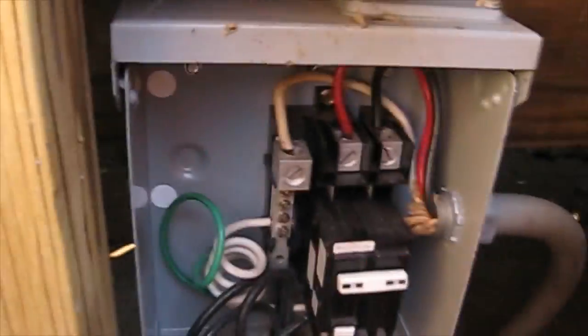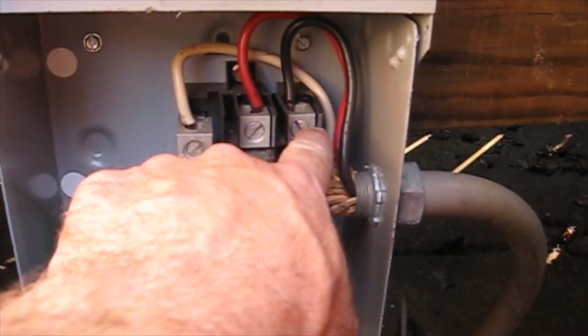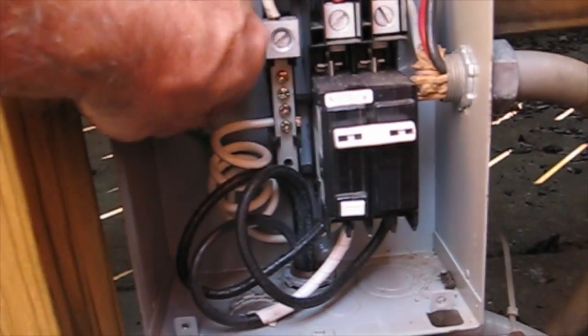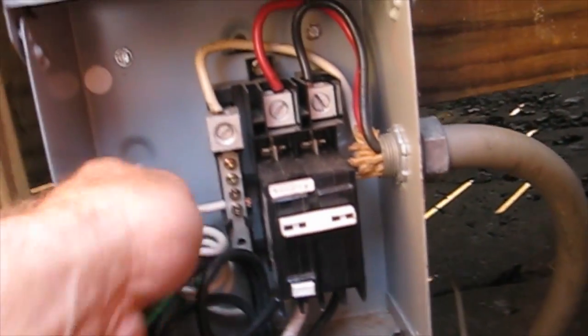And I told you there was no ground. Look, you've got incoming neutral, incoming hot. There's outgoing neutral, your two outgoing hots. Look at this ground right here. That is your outgoing ground to the tub. Not hooked up.